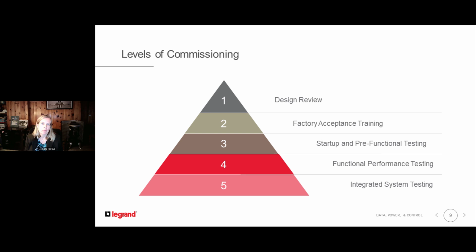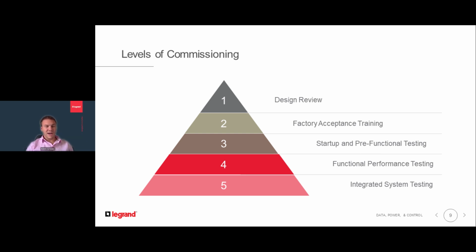Sure. So the other part, after commissioning, after the systems in your building have been handed over to your customer, one other thing you need to consider is maintenance of it all, right? Each system has its own type of maintenance. We're talking about overhead busway here. In this particular instance, it's a very static system. But what I find oftentimes is a lot of spec engineers telling the end user, hey, you don't have to maintain it. It's maintenance free.